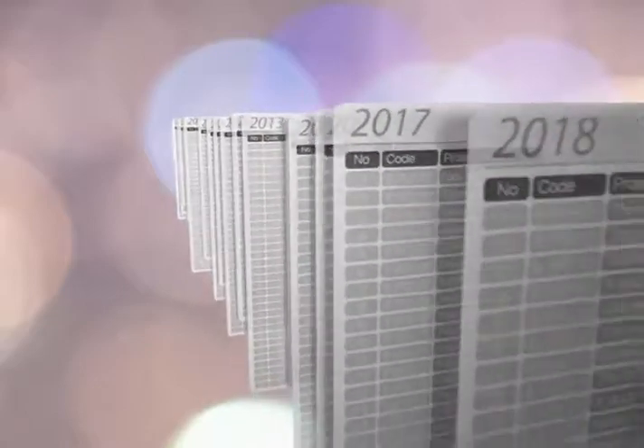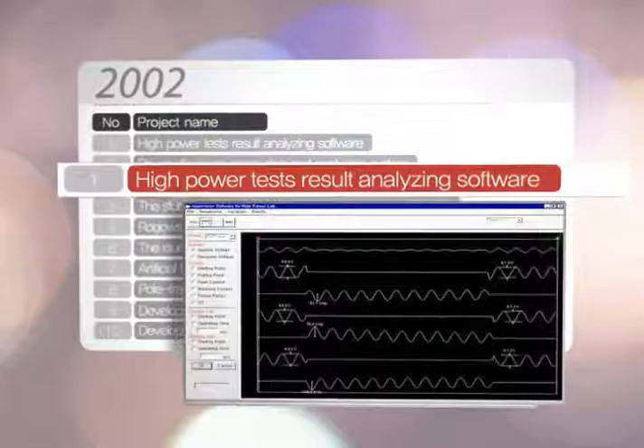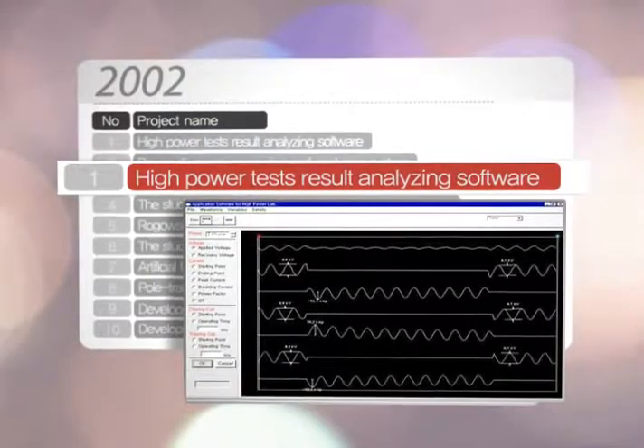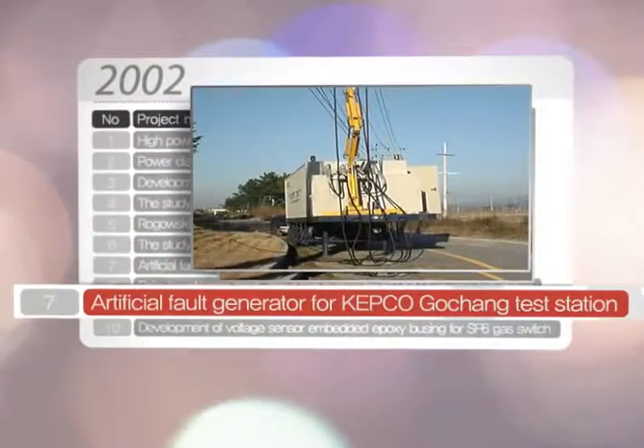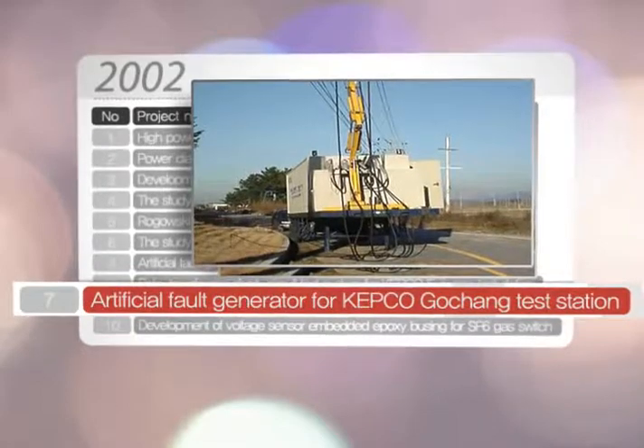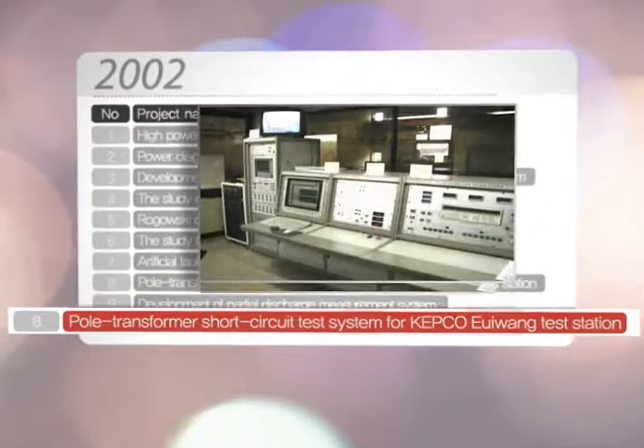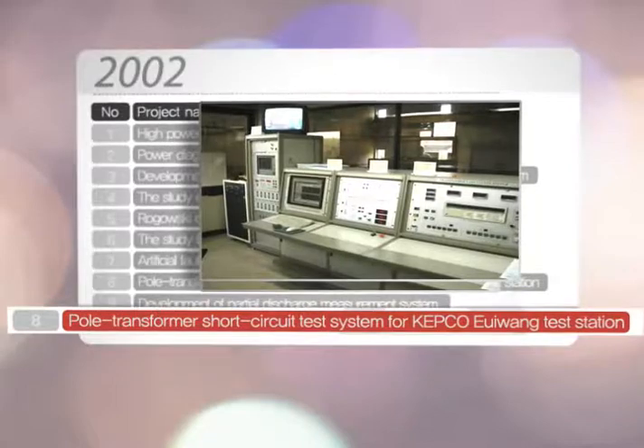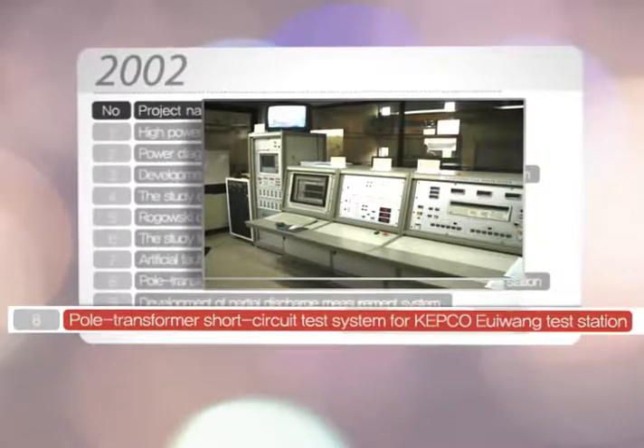PT&T also performs research and development works to shorten the test time consumption, to save the investment, to develop necessary techniques in advance, and to give solutions for the failed tests. For example, high-power tests result analyzing software, artificial fault generator for KEPCO Gochang test station. We have developed a pole transformer short-circuit test system for KEPCO Uiwang test station.